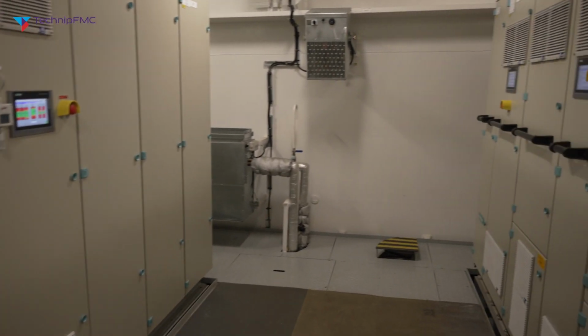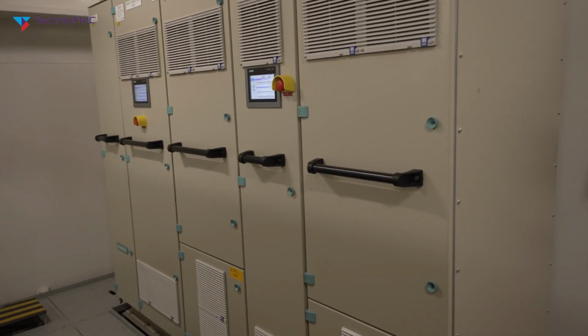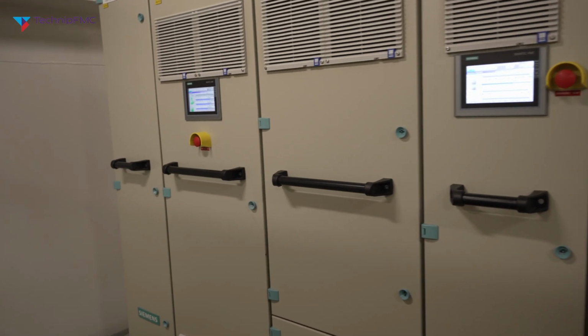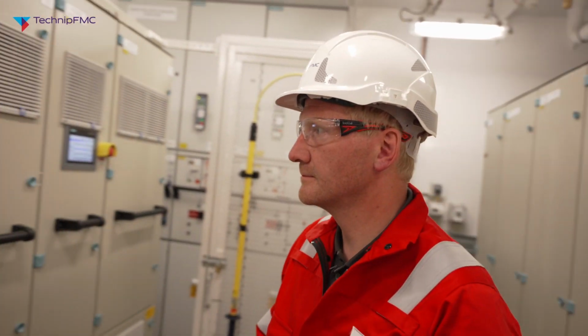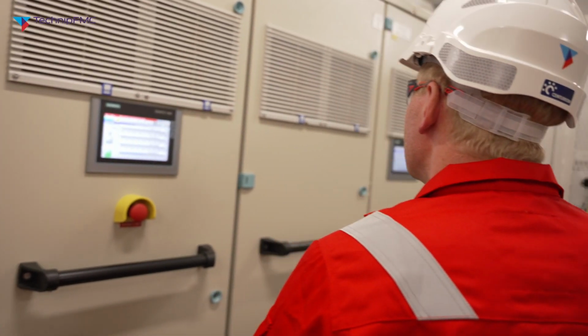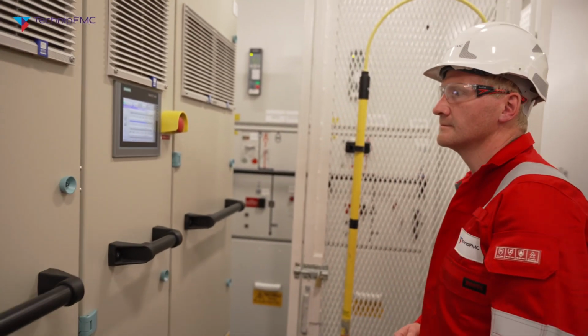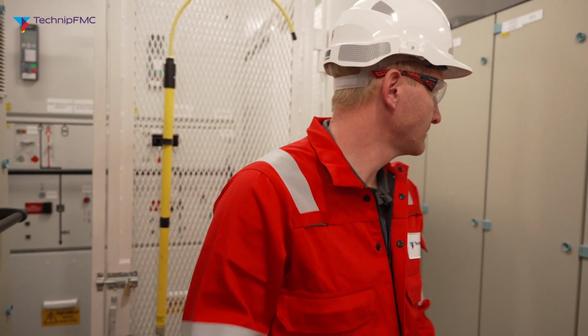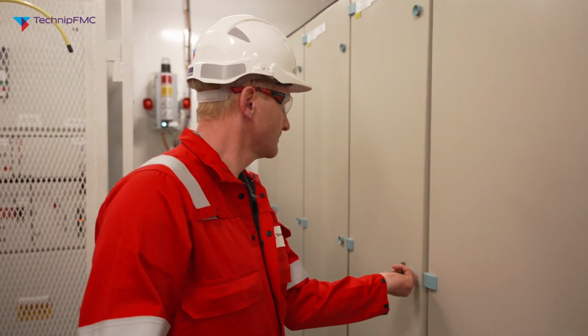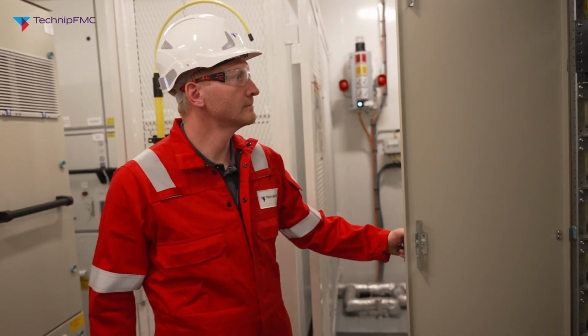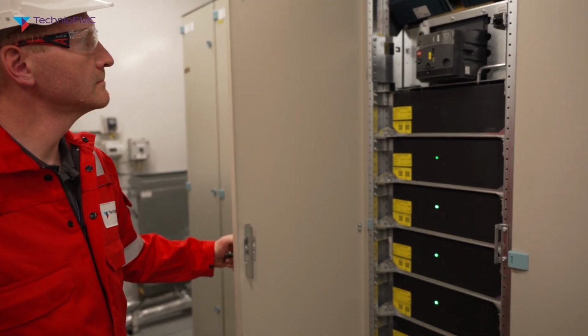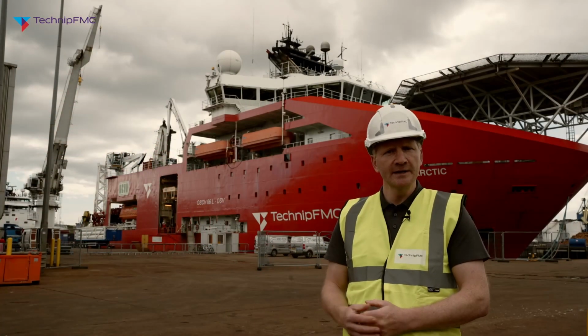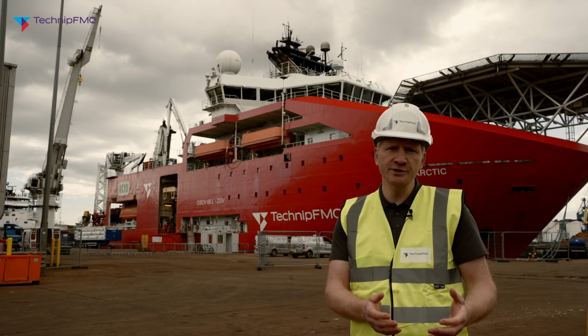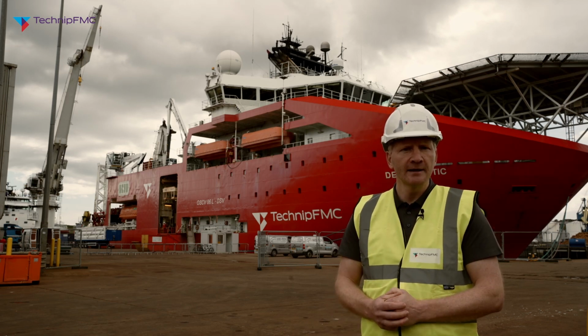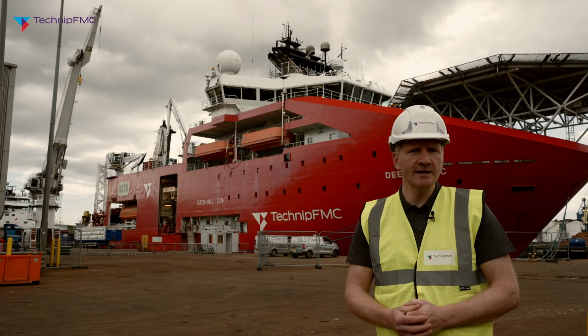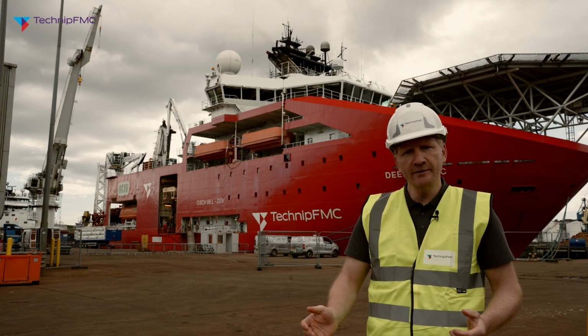Within each of the battery rooms on board, we've got two cubicles of batteries, and in there we have around 420 kilowatt hours of energy storage in each battery array. It's a lithium-based technology, and like a lot of other lithium-based applications, we can't use all of that energy storage. If we cycle the batteries full to empty too many times, we'll quickly degrade them and shorten their life. So we protect them with depth of discharge margins, max charging margins, and we also build in an aging allowance, because we expect wear and tear and degradation on the batteries through their life.